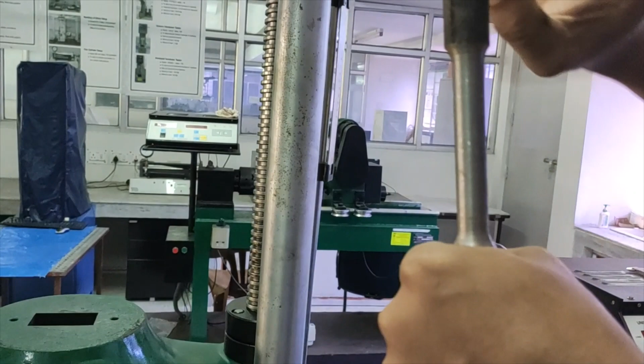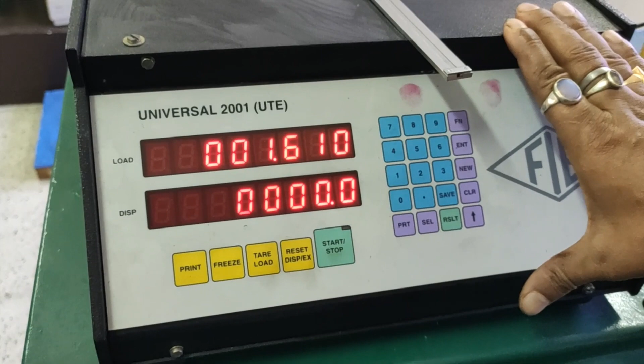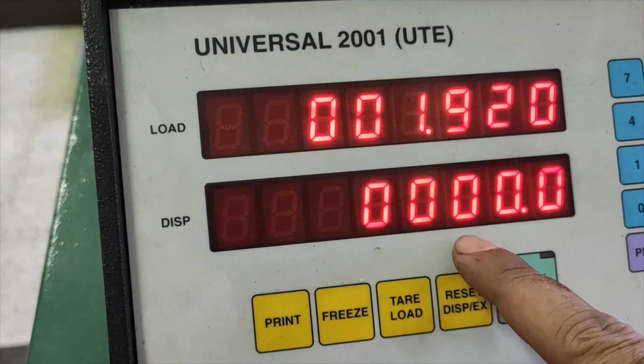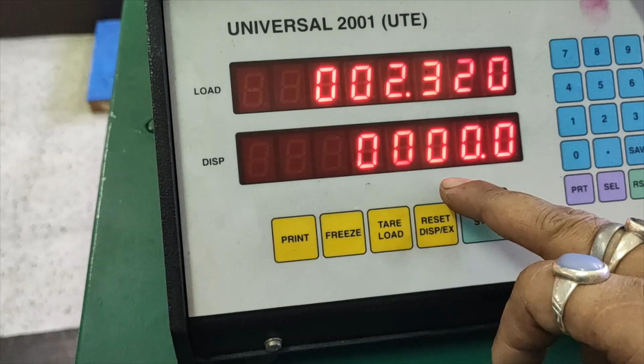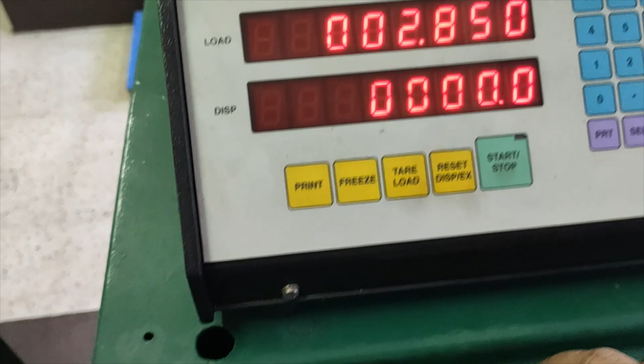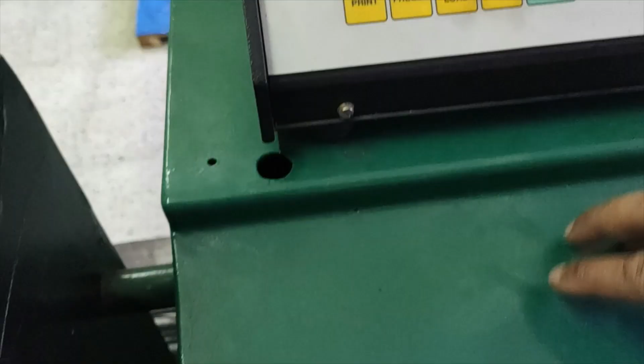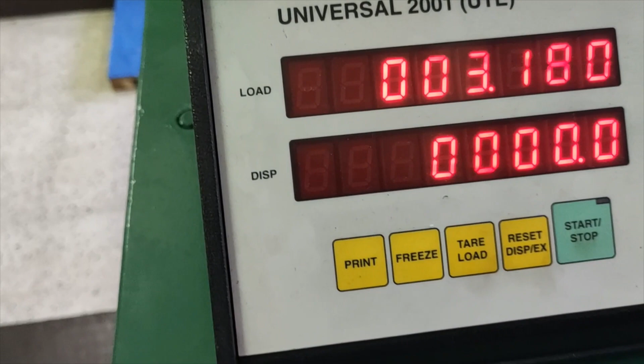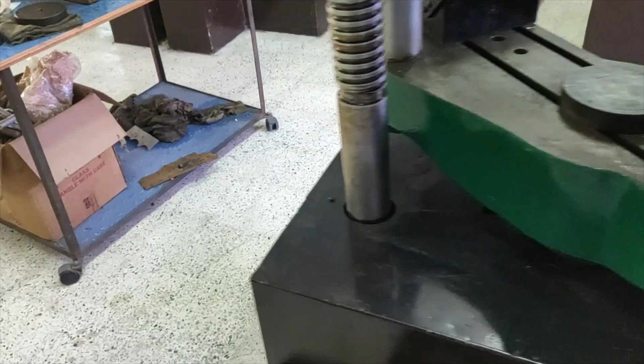So this way we will perform the experiment. This is the data acquisition system cum controller, where we can see the load in kilonewton and the displacement. These physical values come from sensors - load comes from a pressure transducer fitted inside the machine, and displacement comes from a rotary encoder, a linear encoder attached here.